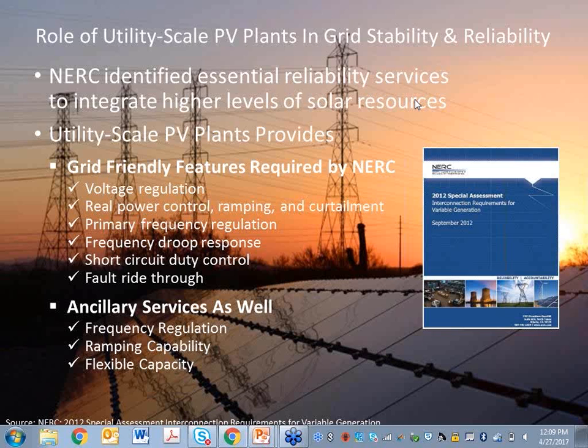To build on that, one of the tests we did was taking that plant all the way down to 5 megawatts. At 5 megawatts, it was able to provide full reactive capability, taking in 100 megawatts of reactive power and also producing 100 megawatts reactive. So at night, the plant could take a small amount of megawatts from the grid, convert it, and provide full reactive capability as though it were operating at full capacity.